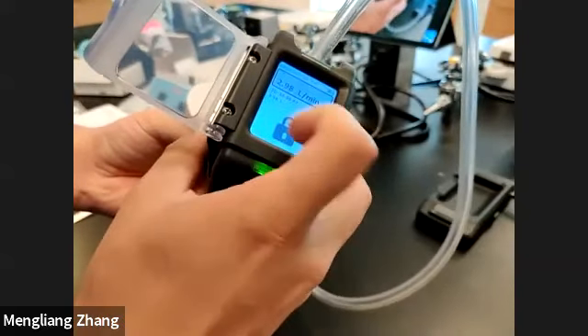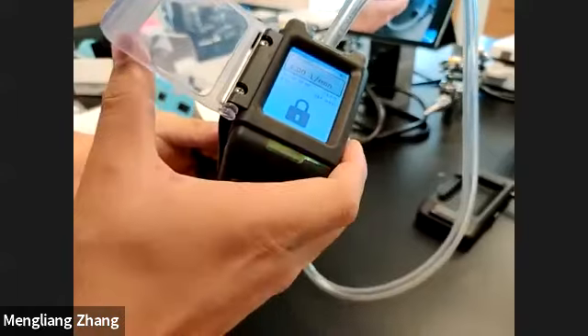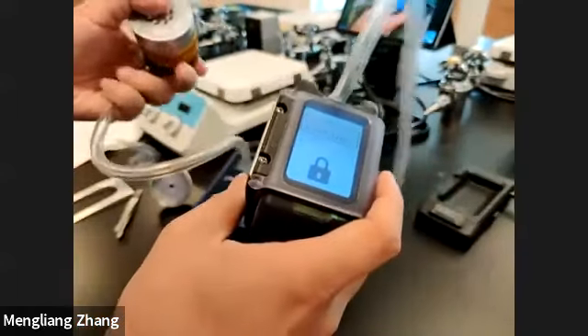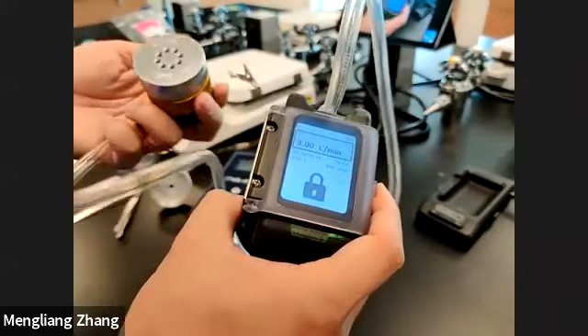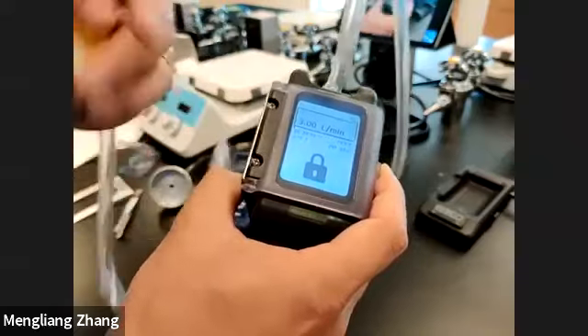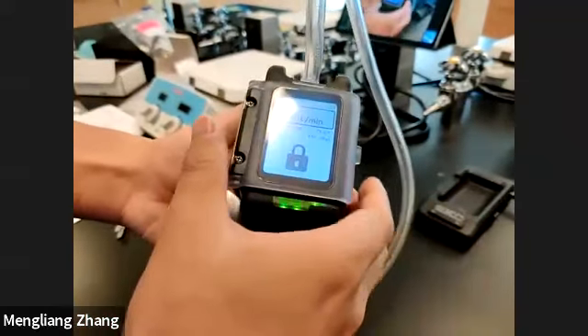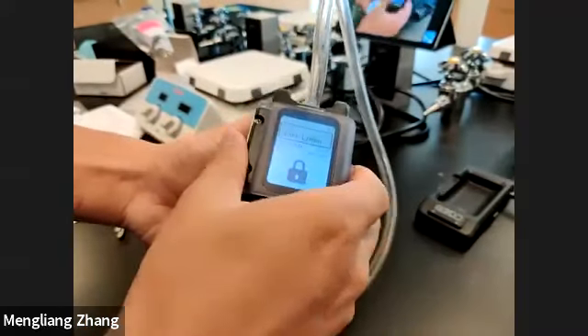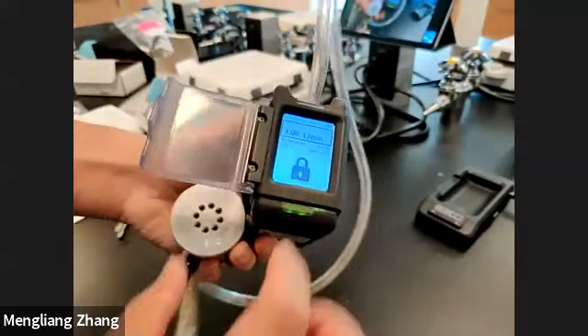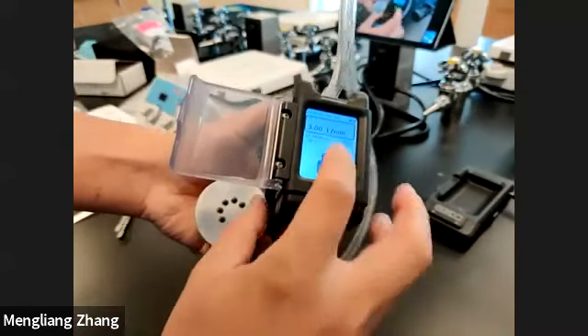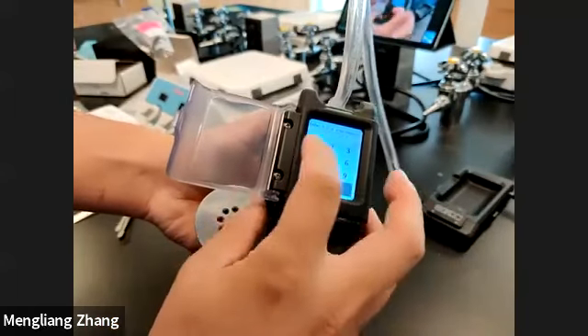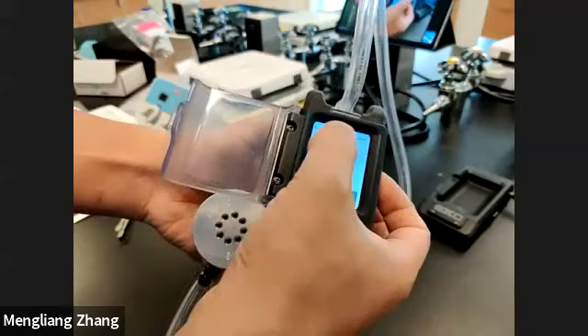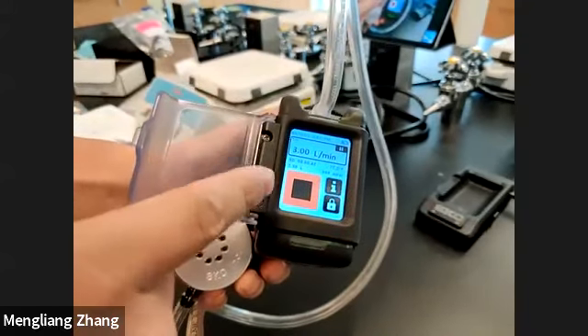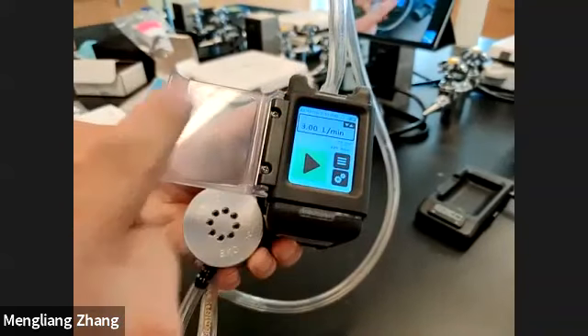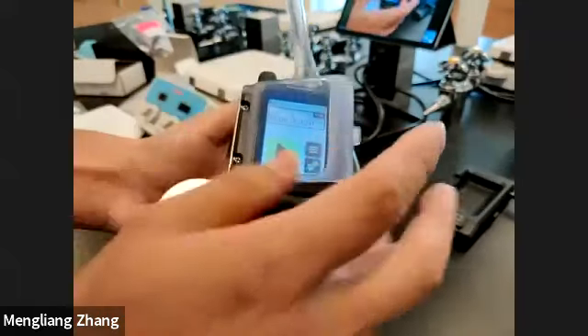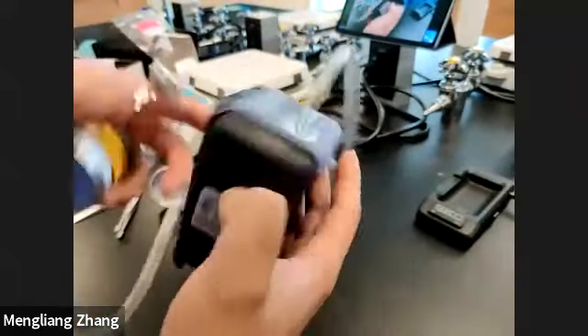Okay, so the screen is locked after you click the run button. All you need to do is close the window and let it run for 8 hours. It will automatically stop after 8 hours because the setting is 8 hours. If you want to stop the sample collection before the 8-hour timeline, you just open the cover, and the screen is locked, so you need to unlock it. You just touch the screen, and to unlock it, you press 1, 2, 3, 4. Then the screen is active, so you can press the stop button here. It will stop the pump and stop the sample collection. Then you close it and press the power button to turn off the pump.